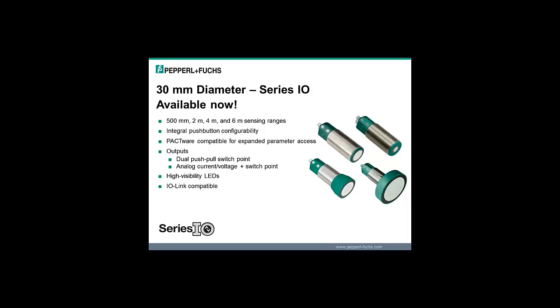These give you the same functionality, but with a push button. So they're very well sealed. There's no plug to come loose or fall off or drop. So that's the big feature of this product that will be a successor to the plug type, is it's all push button, nice membrane type push buttons that are very well sealed to the environment. They are configured either by the buttons, or if you want to go with the software, there's a program called Pactware that, again, if you take the intermediate and the advanced classes, you'll learn all about that. But you can do probably 90% of what you need with the buttons, and you don't need the software whatsoever.